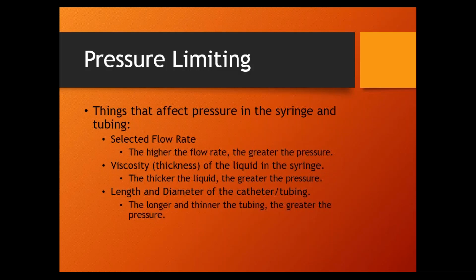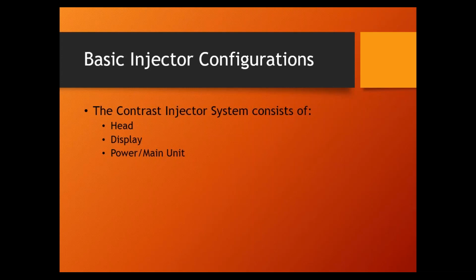All right. We went through all this. So the flow rate, things that affect pressure limit. We talked about this. The flow rate, the thickness of the fluid in it, viscosity, and the length and diameter of the catheter tubing. All right, now, every contrast injector, and I think this is true, I can't think of any exceptions, every single contrast injector system has 3 parts. None of them have 2, none of them have 4, all have 3, right? There's the injector head, there's the display, and there's what's generically referred to as the main unit or the power. Right? Those are those 3 components.